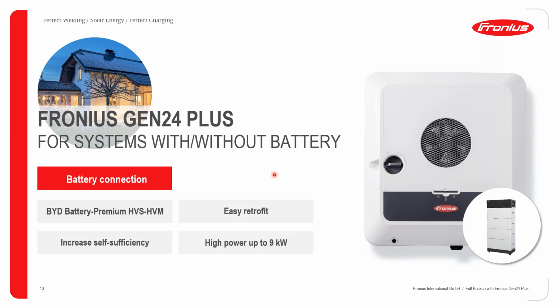So the GEN24 Plus can be used with or without batteries. If you use the system without batteries, you do not get your full backup. Okay, you'll only get your PV point backup, which is limited to 3 kilowatts. If, however, you do install batteries, you get the full system backup. And the only battery we are compatible with is the BYD Battery Premium HVS and HVM. It's extremely easy to install. You can increase your self-sufficiency in this sort of system. And we can give you a high power up to 9 kilowatts on our 3-phase GEN24 Plus inverter.